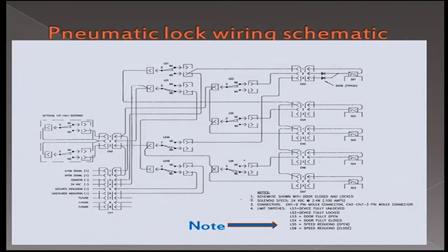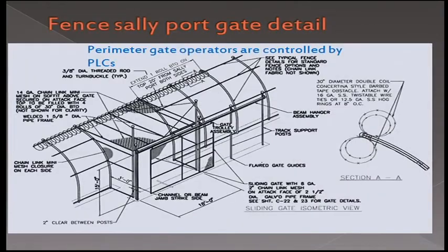Also note here, the thing that we're pointing out is... you can't read it, so we'll read it. It says speed reducing. The motors on the doors, you can control those and control the speed of it. So you could crank it up and turn it on and essentially blow out the motors on the doors so that the doors are no longer functional at all. It's called a cascade program, so the doors don't all open up or slam at once. That's what it's doing.